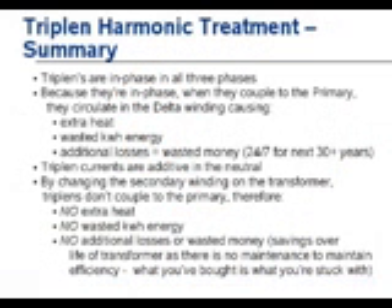This allows the transformer to return to its natural efficiency of around 98%. To summarize the triplen harmonic treatment: triplens are in phase in all three phases. Because of this nature, they have a tendency to couple into the primary, and when they do, the delta winding causes a lot of additional heat, a lot of additional wasted kilowatt energy — meaning a lot of additional wasted money for 24 hours a day for quite a long time.